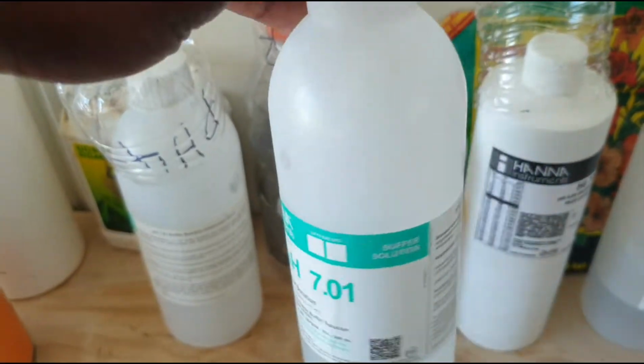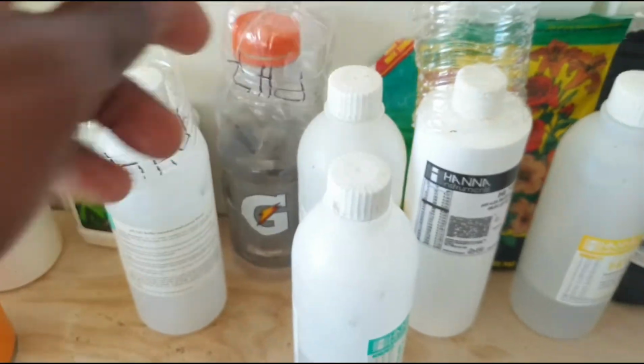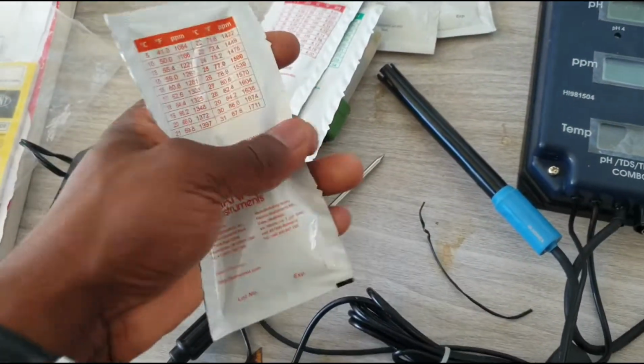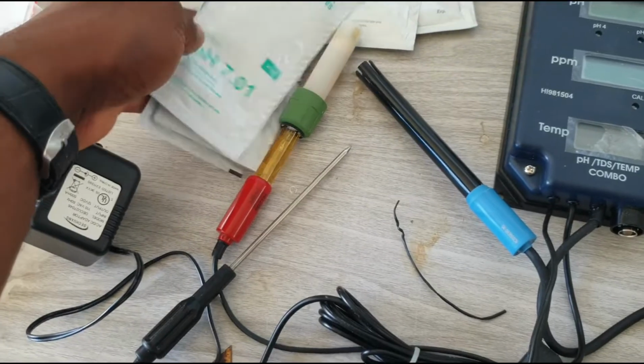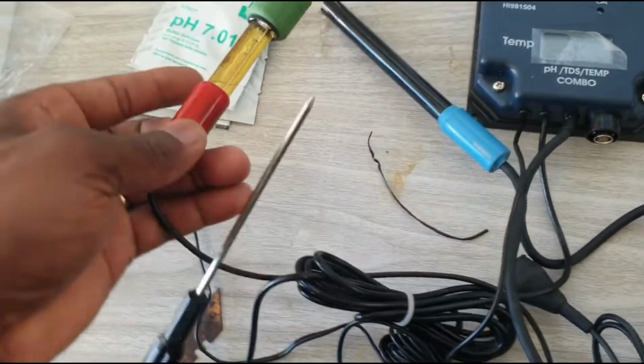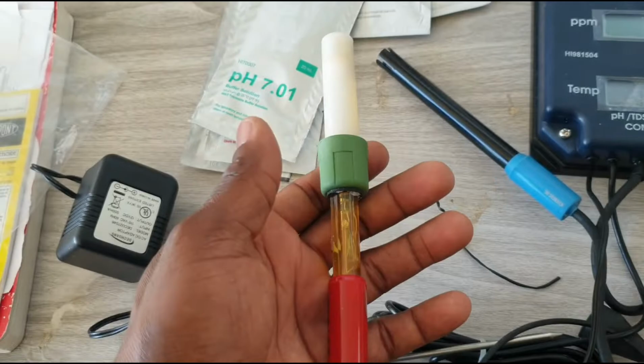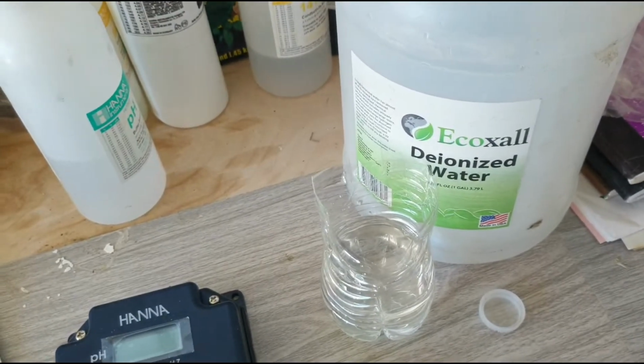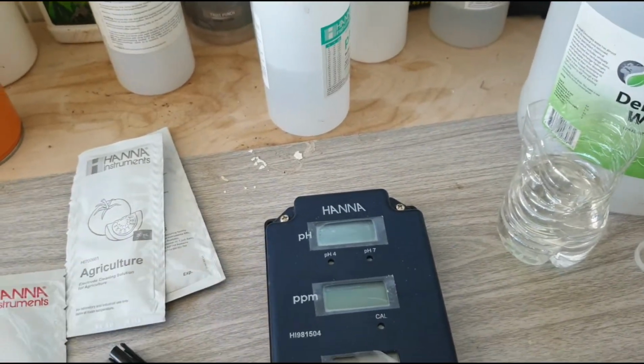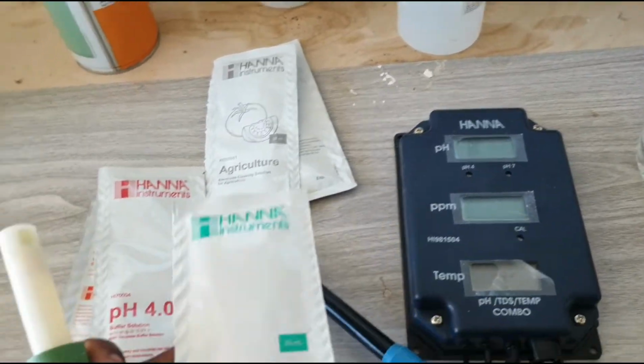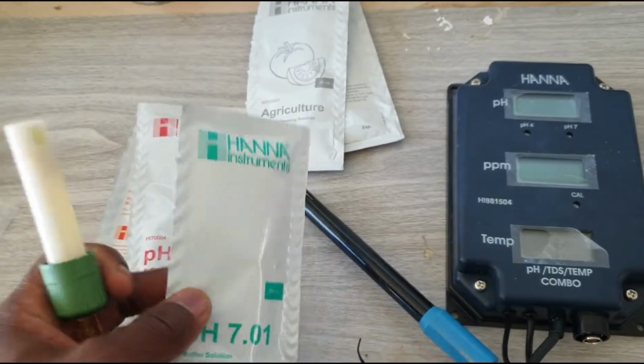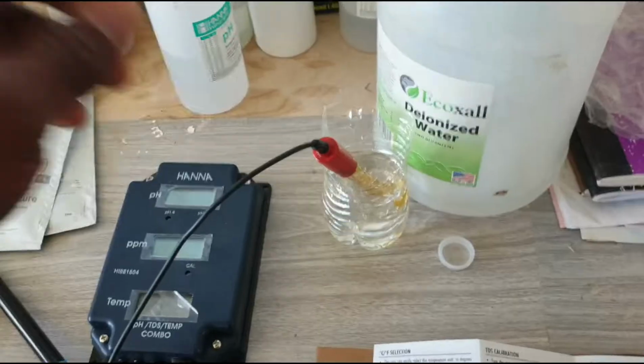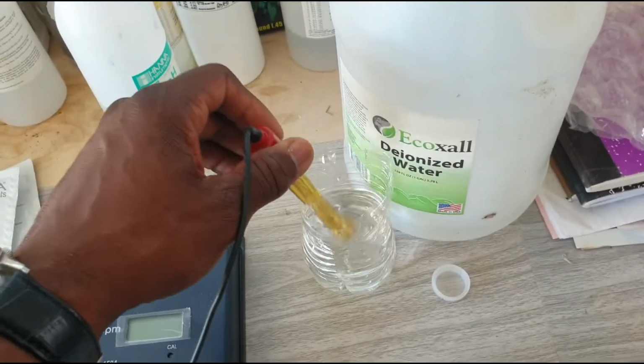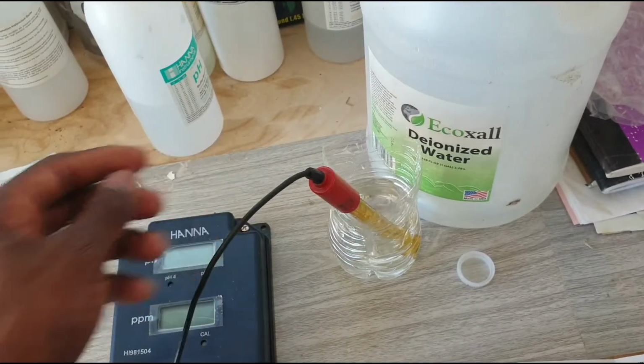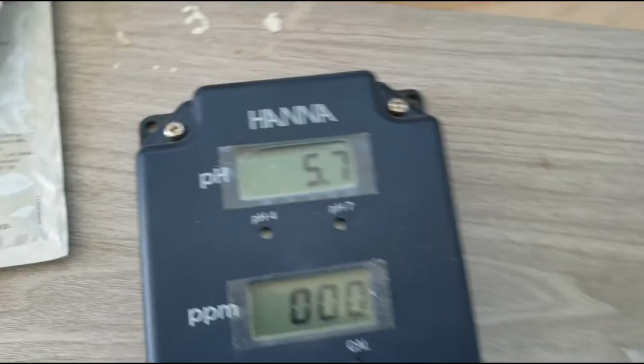The only time you'll have to do that is when you have the solutions in bottles like this. You can throw them out. But in a packet like this, you can just dip the probe in it. So first things first, we are going to wash off the pH probe, as I said, in some deionized water, and then turn the meter on and put it in the pH 7. Let it stabilize and calibrate it. I'm first washing off the probe inside the deionized water. Then I'm going to put it inside pH 7.